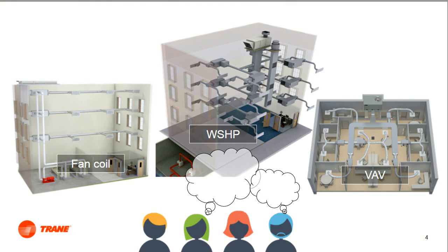Have you ever noticed how in the HVAC industry, we often name air systems based on the zone control equipment used and assume that it's adequate to describe it? Variable air volume system, fan coil systems, water source heat pump system, chilled beams. While this is a way to create a picture in our head, we don't really know if the picture and assumptions that you have are the same as what I have, and it can lead to confusion or misunderstanding. There's just so much to define about a system, including how it's controlled, to really understand the system and how it will perform. The same is true for variable refrigerant flow systems. They come in many forms. So let's take a deeper look at the scope of what we mean when we say VRF system.